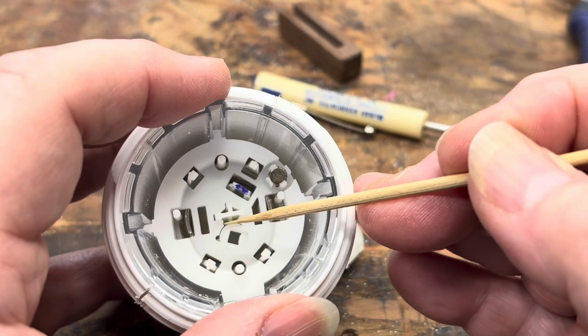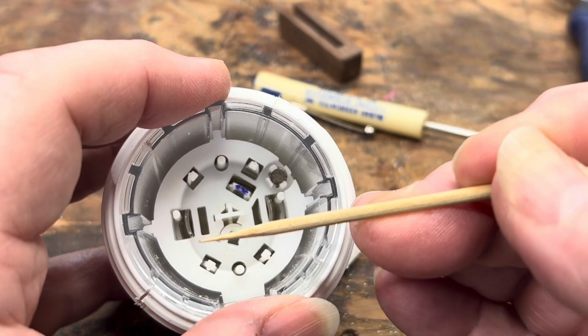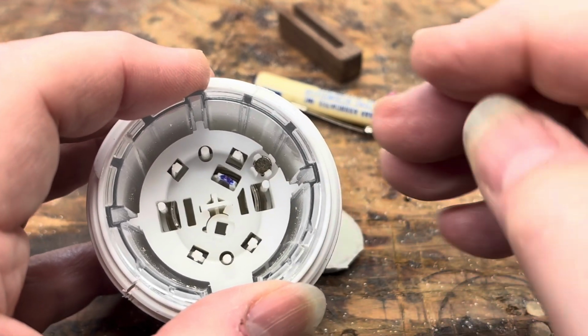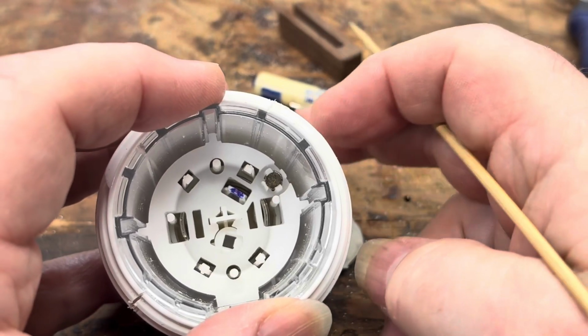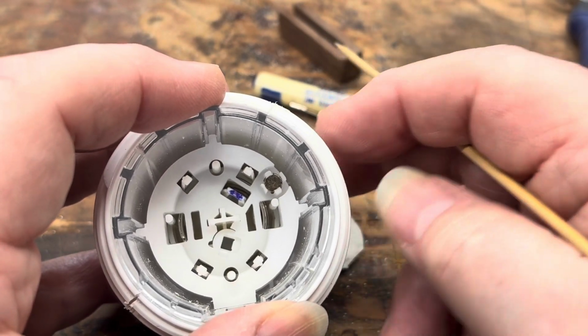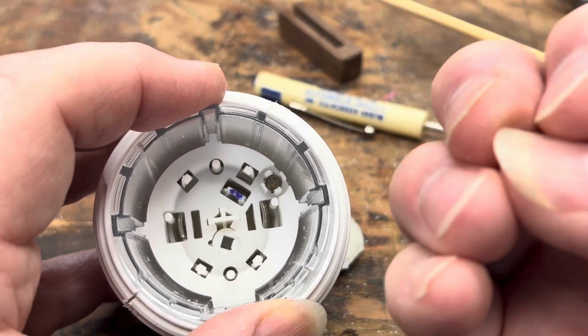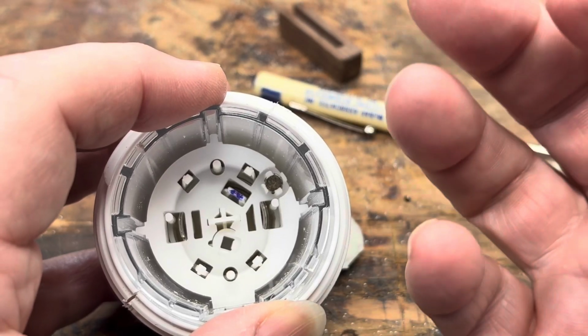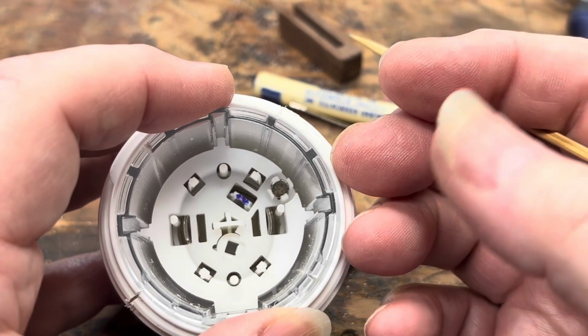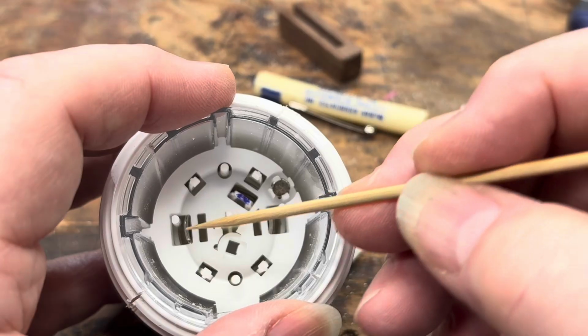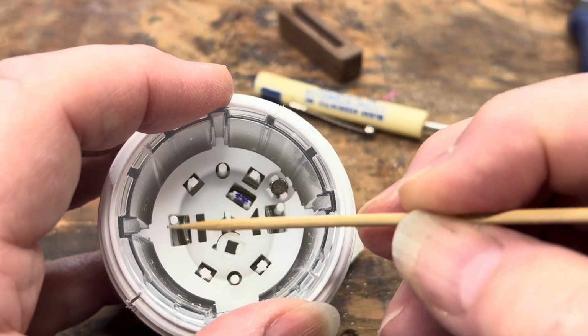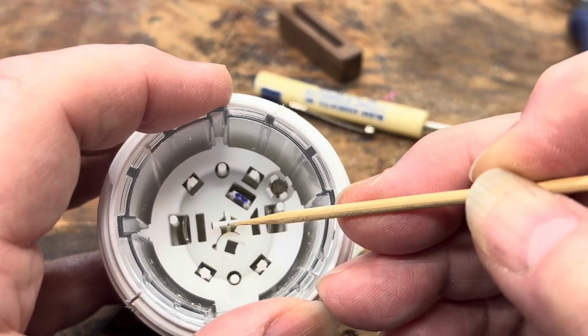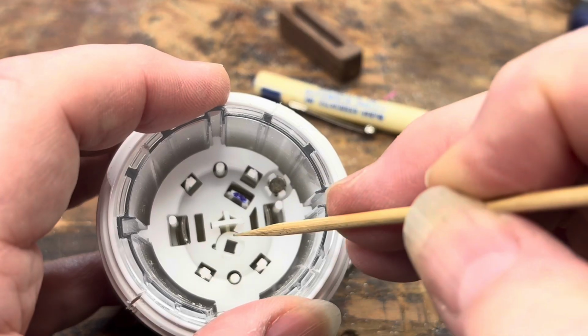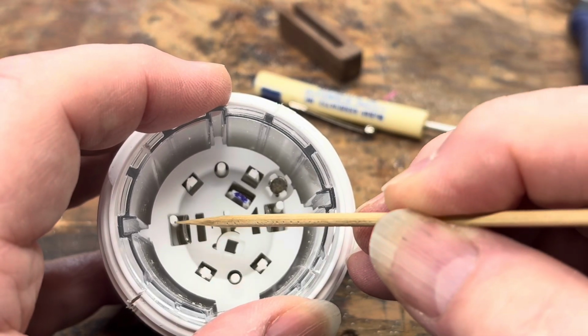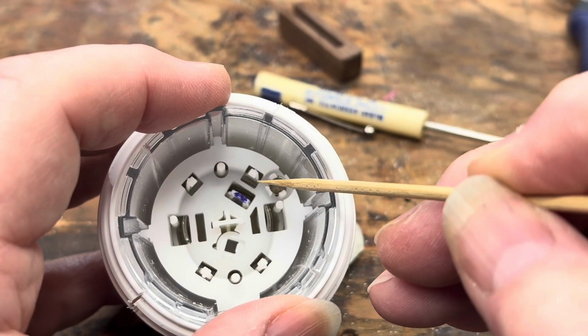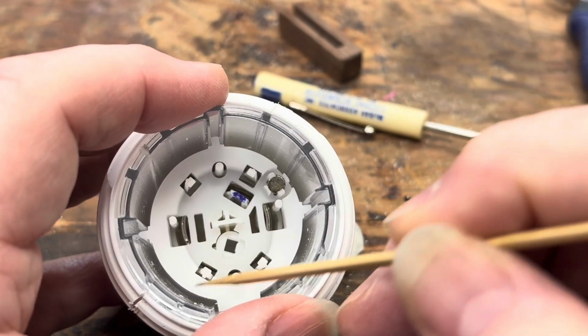Then as this 3-4 comes out towards the patient, that hook coming from cup 2 catches on cup 4, which arrests cup 4's motion, and then releases the spring between 3 and 4. So now 4 is going to withdraw from 3. It's going to let go of all these fingers that are holding the device.